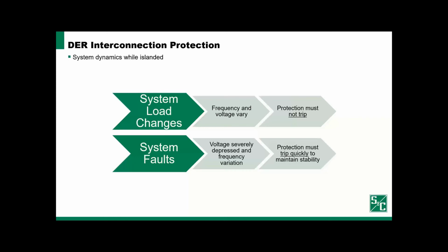Alternatively, during system faults, the voltage will be severely depressed and the frequency will vary significantly, which the protection must trip quickly to maintain stability. The system dynamics when we're islanded, the frequency moves and the voltage moves a lot more than when we're grid tied. So the same voltage and frequency protection settings that may work great when we're grid tied may be challenging and not work effectively when we're islanded.